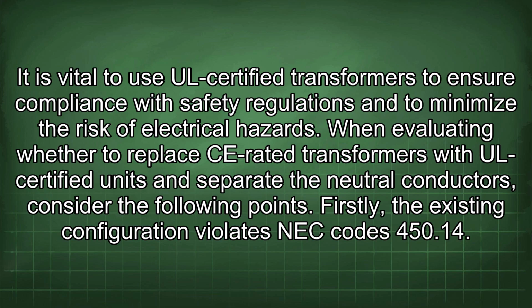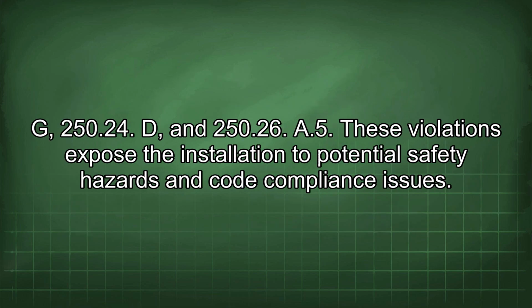It is vital to use UL certified transformers to ensure compliance with safety regulations and to minimize the risk of electrical hazards. When evaluating whether to replace CE-rated transformers with UL certified units and separate the neutral conductors, consider the following points. Firstly, the existing configuration violates NEC codes 450.14(G), 250.24(D), and 250.26(A)(5). These violations expose the installation to potential safety hazards and code compliance issues.